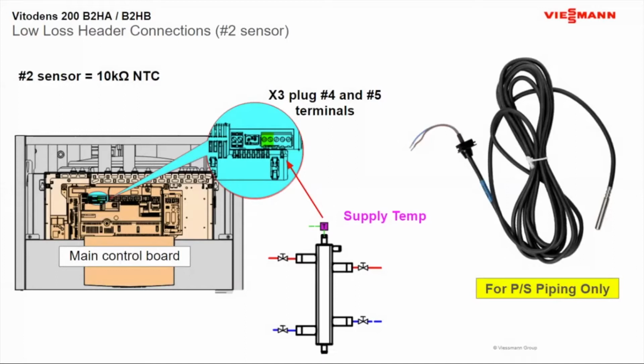Low loss header sensor, if you're going to use it and put it in the low loss header, it's just going to go onto that same X3 plug, on terminals 4 and 5. And that's also a 10,000 ohm NTC resistor. It's pretty neat the way this works. It's always maintaining a certain temperature right here in your low loss header, or even if you were using a buffer tank. I know a lot of guys in Alaska use buffer tanks for their radiant, so you can use that same thing as a low loss header. And the nice thing is it's always maintaining the right temperature here. With our smaller ones for the smaller boilers, it's always in the flow going out to your system to check the temperature going out, to make sure that you're getting the most accurate temperatures going out to your system.